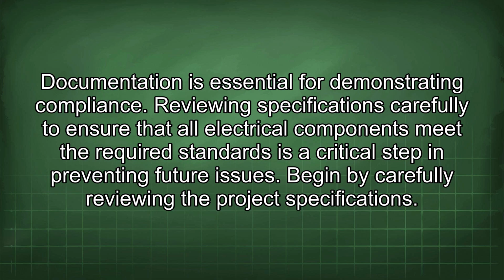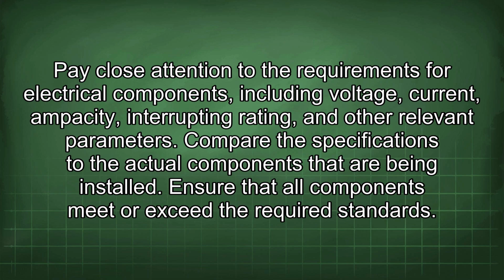Reviewing specifications carefully to ensure that all electrical components meet the required standards is a critical step in preventing future issues. Begin by carefully reviewing the project specifications. Pay close attention to the requirements for electrical components, including voltage, current, ampacity, interrupting rating, and other relevant parameters. Compare the specifications to the actual components being installed, and ensure that all components meet or exceed the required standards.